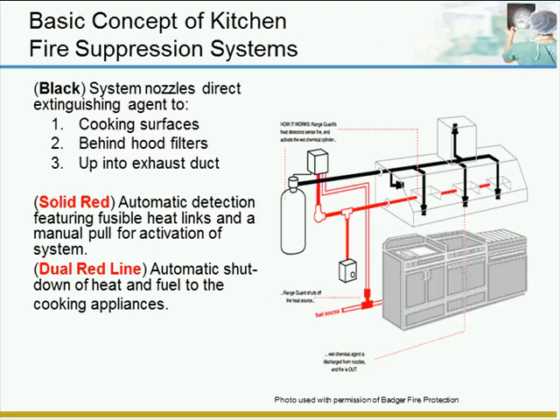This slide shows a typical cooking system, which is the gray portion of the diagram on the lower right. The red piping is the fuel source, and the electronics from the fuel source into the wet chemical extinguishing system. And the black piping from the bottle on the left shows the piping and nozzle locations to dispense the wet chemical. It should be noted that this is a one-shot extinguishing attempt. If there is a fire and the system is activated manually or from the fusible links in the hood, once the contents of that bottle have been expended, there is no more wet chemical capability. And if the fire is not fully extinguished or controlled, you will then be relying on your sprinkler system.